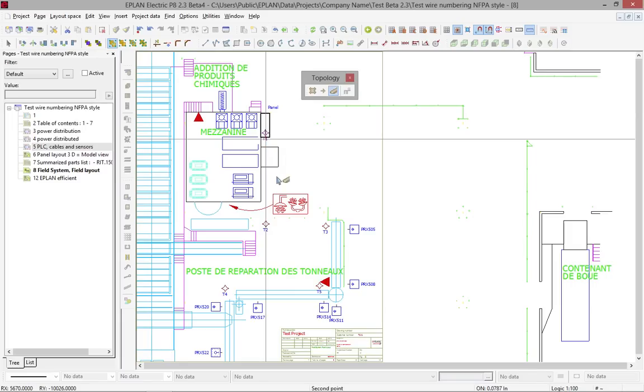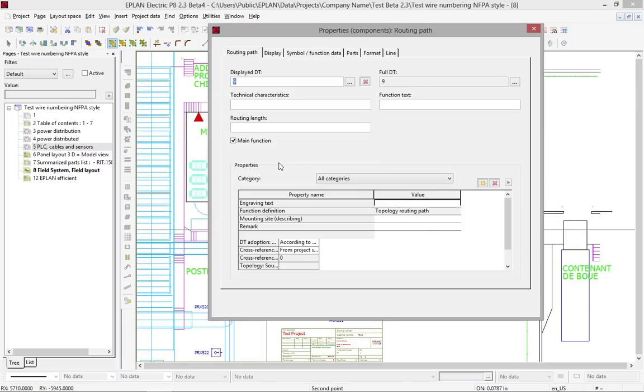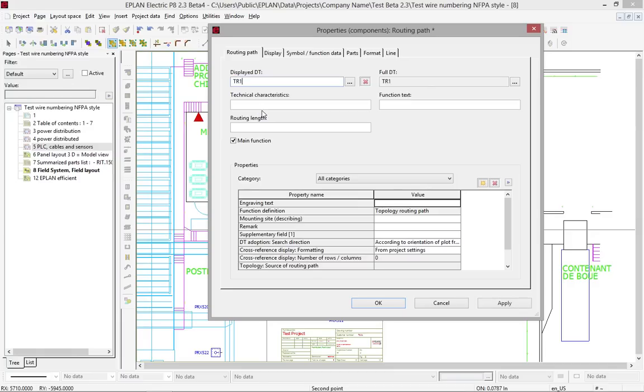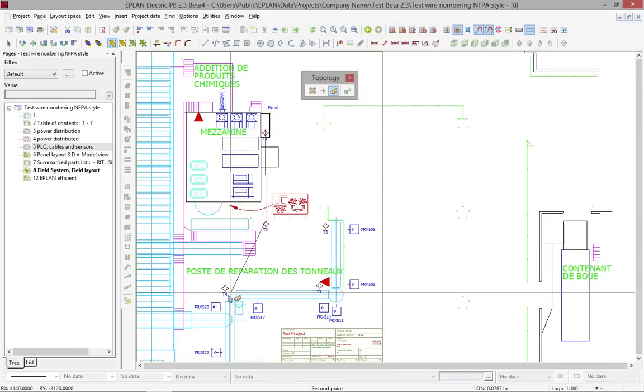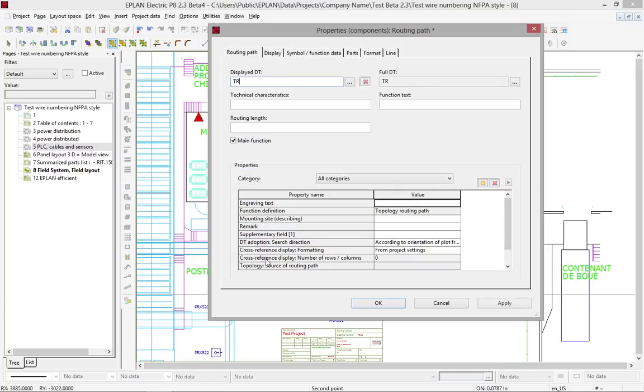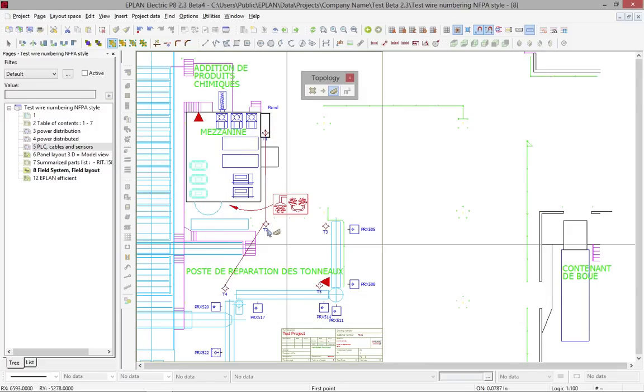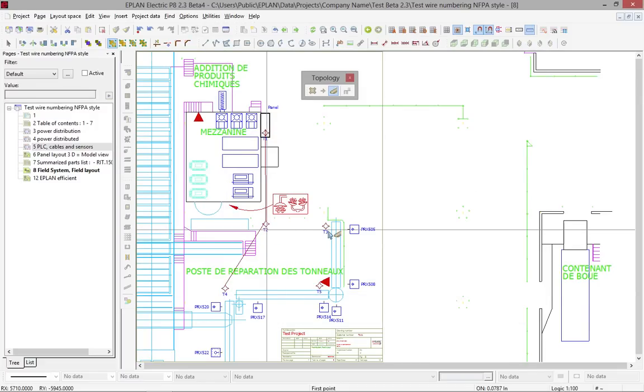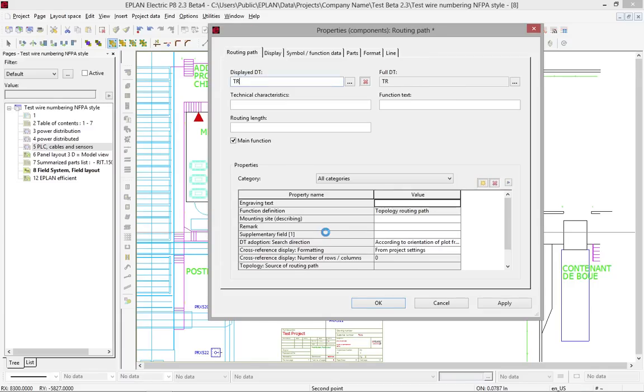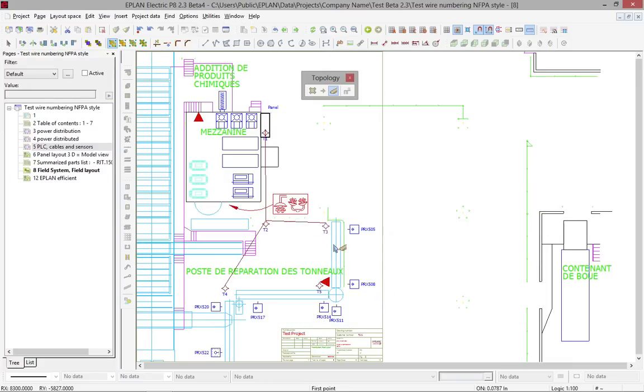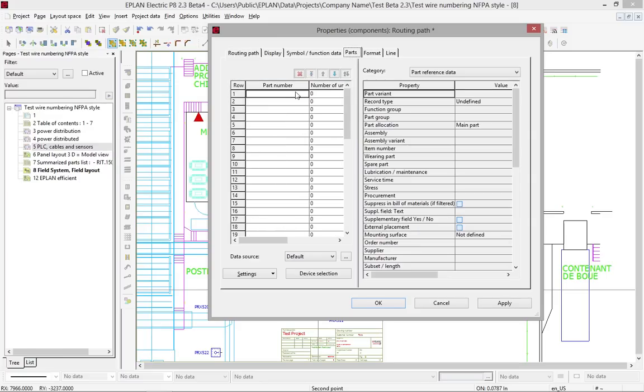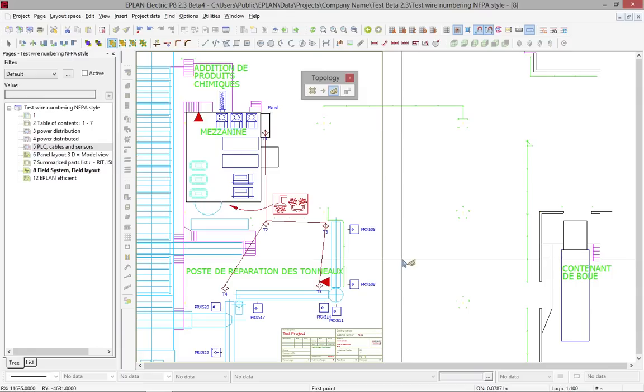The next step is actually to run the different cable runs or cable trays. Here I can say this is my tray number one. The tray number two will actually go and link up this guy here. I could call it tray number two. The next one will be tray here, number three. You can see that you can assign some part numbers. So this would be basically a specific cable tray or it could be a PVC tube. It could be any kind of material that is related to that portion of the tray. You're not only limited to one small part - you can assign as many parts as you want. So all the accessories and everything can be assigned to it.